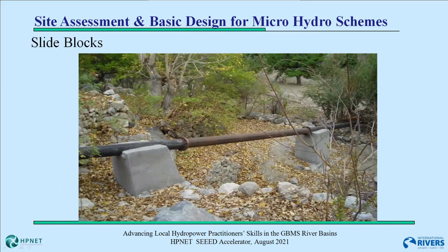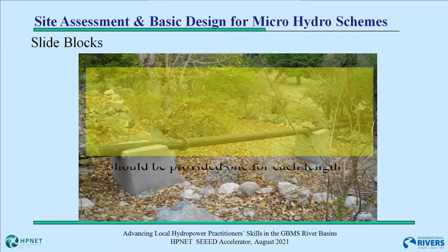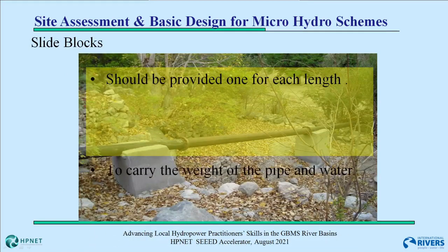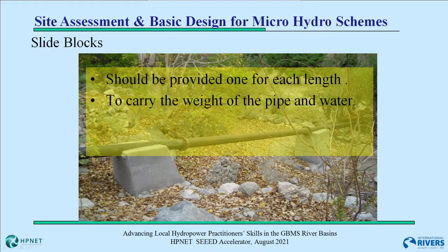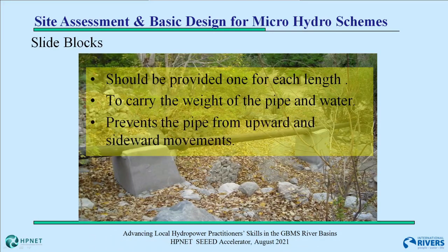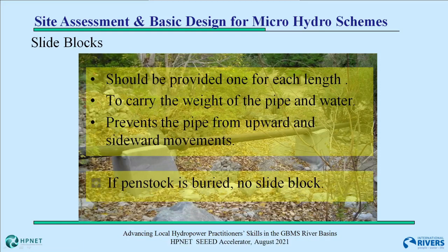Slide blocks, also called support blocks, should be provided for each length. The reason is to safely carry the weight of water and the pipe. Slide blocks prevent the upward and sideways movement but allow a small lateral movement. If the penstock is buried underground, obviously there is no need for slide blocks.